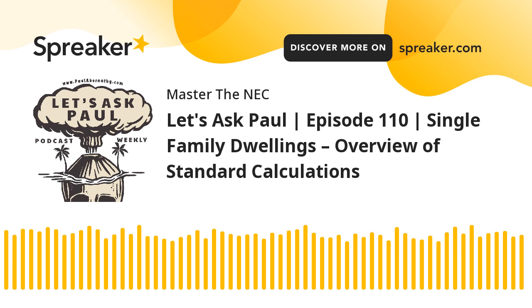So if you look at 220.50, basically it's saying, okay, look for the largest motor in this dwelling, and I want you to take its value and I want you to multiply it by 25%. And you're saying, where does it say that? Well, it doesn't have to say that because it's basically referencing you to 430.24, right? And if you keep it simple, what does 430.24 tell us? You take the largest motor at 125% and the sum of the other motors in the group, right? Well, all of these motors are going to be in the same group because they're all connected to the same service. So they're all in the same group.